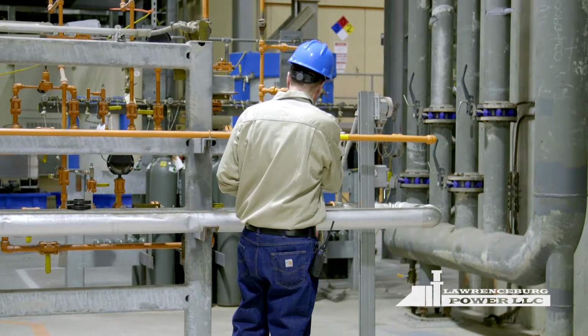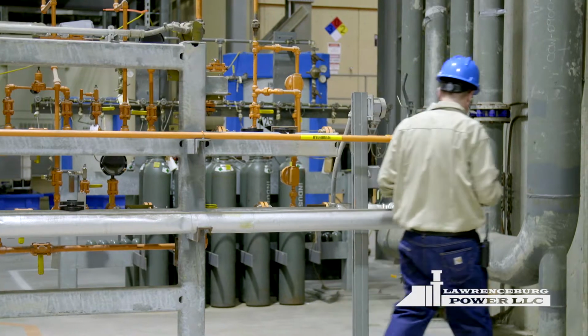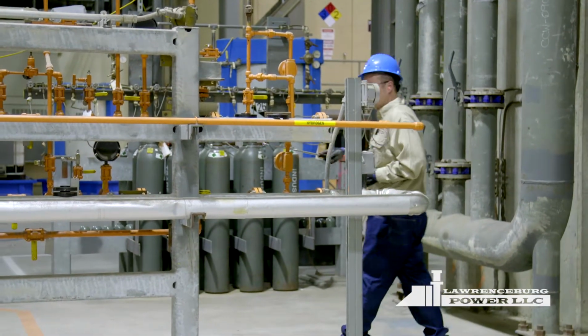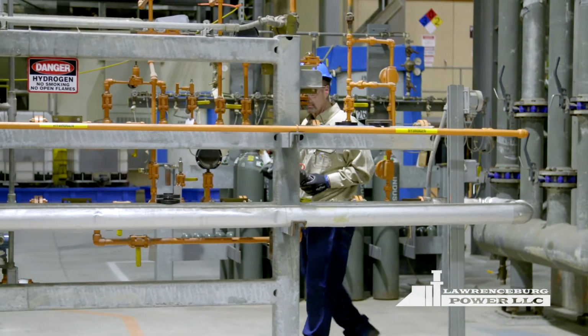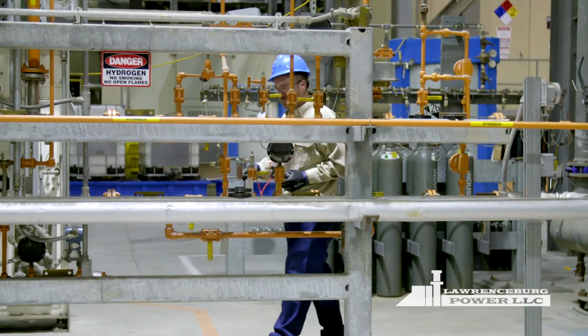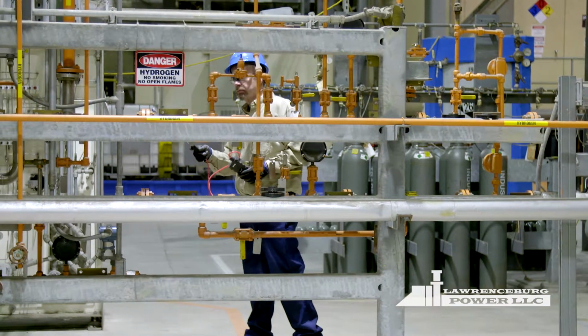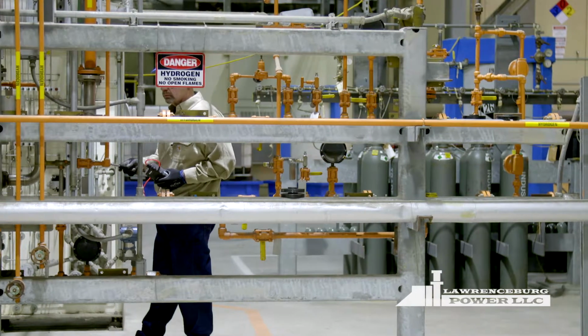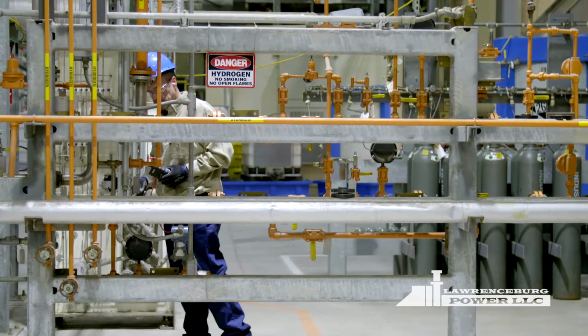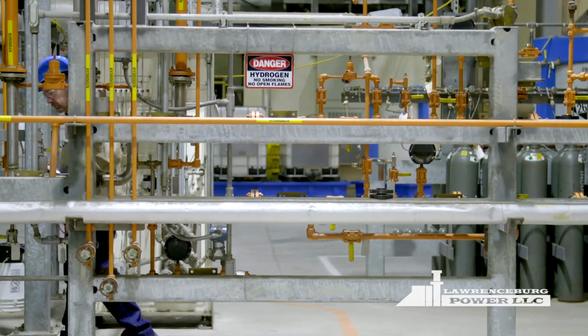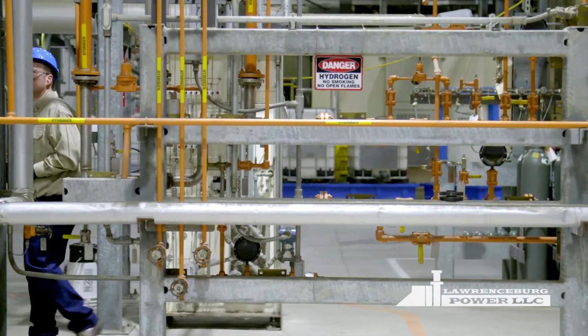Review instructions for gas monitor applications and proper use during your job safety briefings. Workers must know how to operate the gas monitoring, including calibration, air sampling, and alarm response procedures. When leakage is detected, remove all ignition sources, exit the area, and report to plant operations.